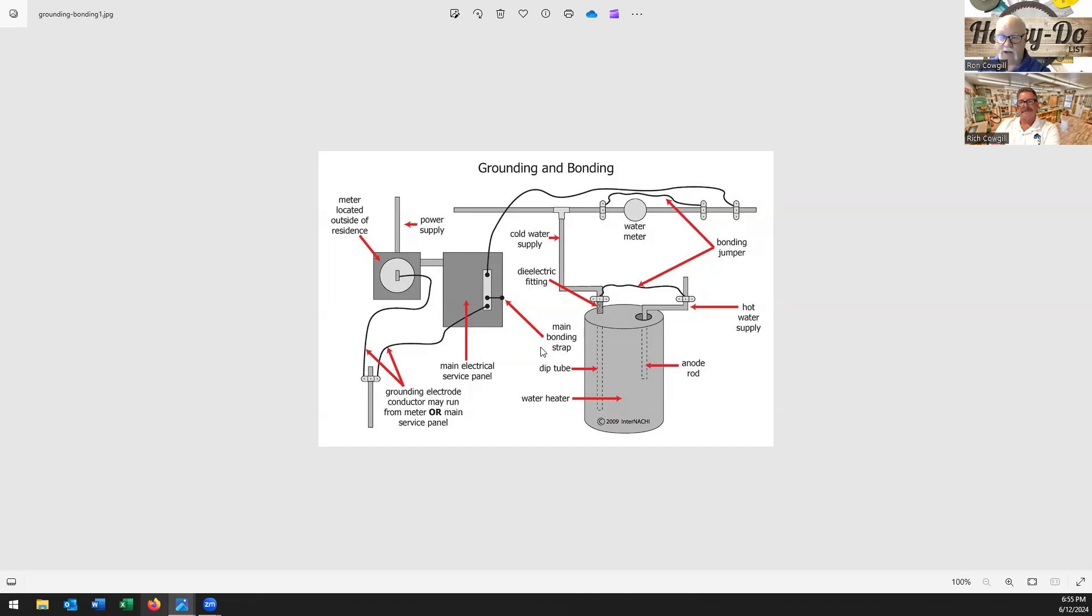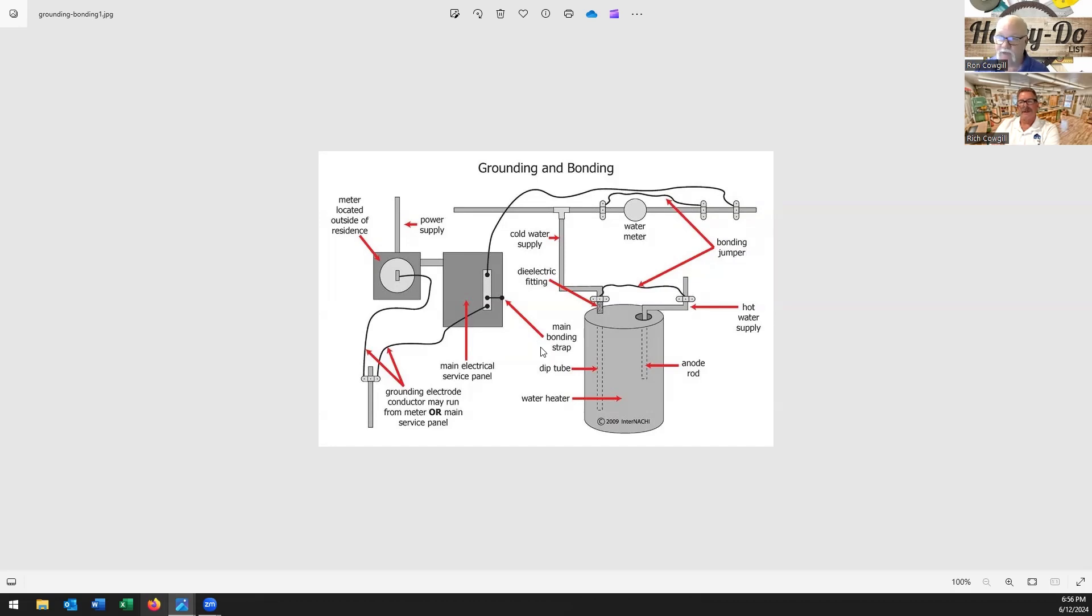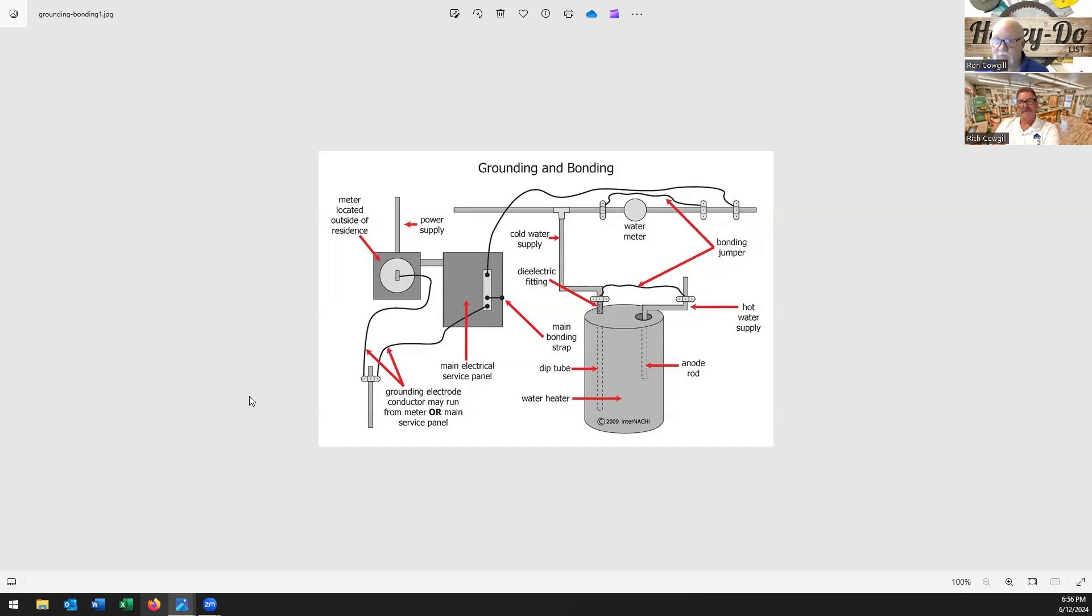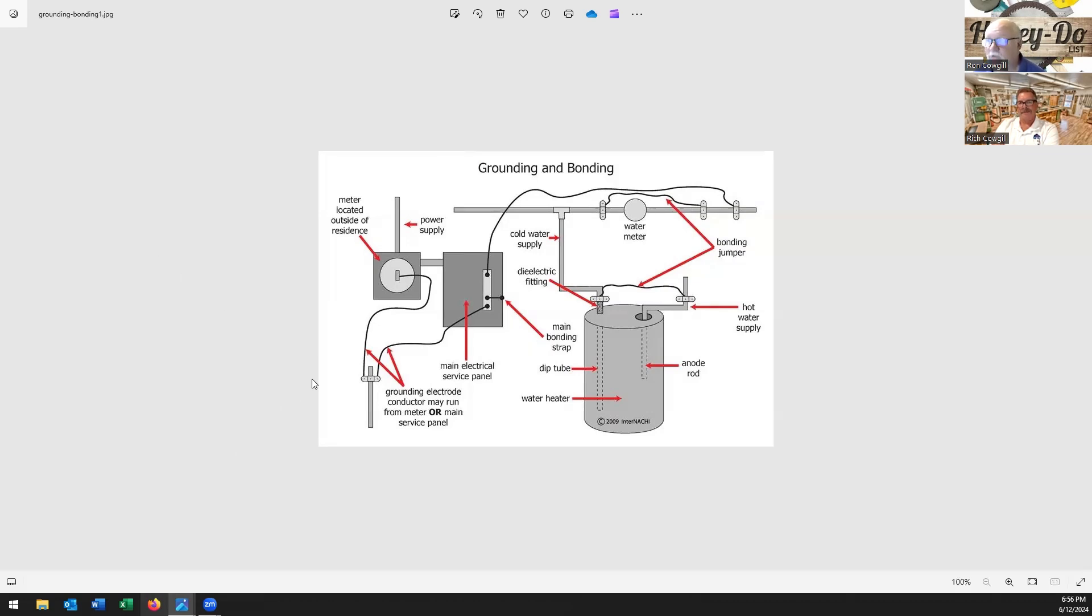Someone opened up an electrical oven that they had and it had a ground - an isolated ground - coming from the panel to the outlet. And he had some friends that were telling him he needed to then put a jumper from that to the electric box also. But that's already bonded back to the panel. There's no reason to tie those two together. If there was an electrical shock, you know, now you no longer have an isolated ground from your appliance back to the panel because you bonded it to the electrical box. So you don't want to do that. So if you have a four conductor outlet it has a ground, you put your ground in there - that's isolated back to the panel.